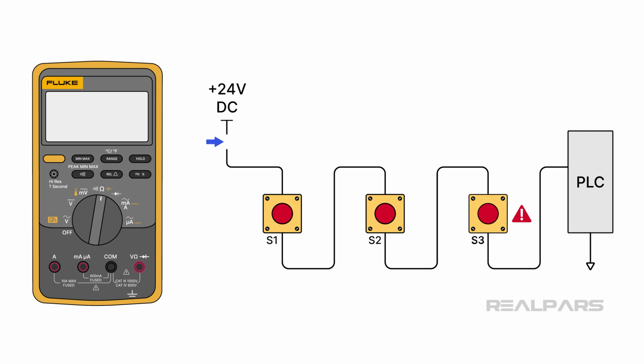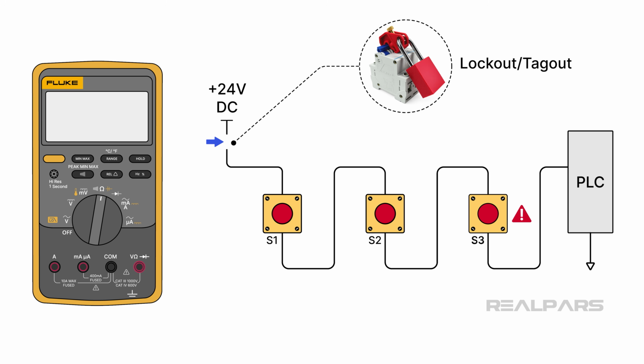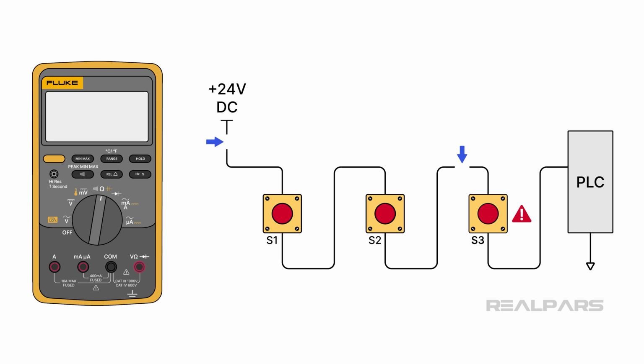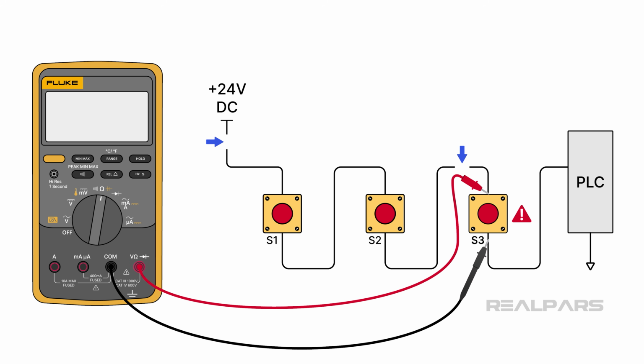Okay, let's assume you've removed the power supply and followed your plant's lockout-tagout or LOTO procedures. Disconnect at least one wire from S3's terminals. Connect the DMM probes directly across S3's screw terminals. Not surprisingly, the meter displays open load, or OL. Some people will tell you to use the DMM's convenient continuity feature, which gives a beep for continuity and silence for an open circuit. That test is certainly valid in our example.